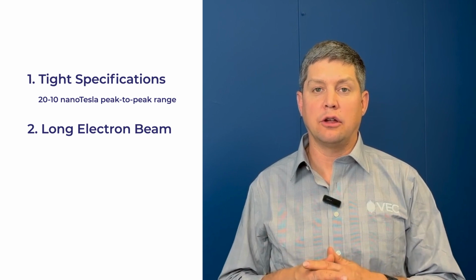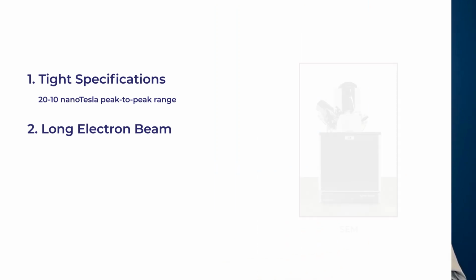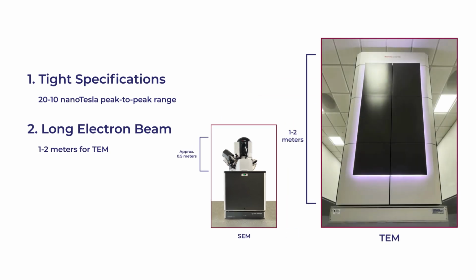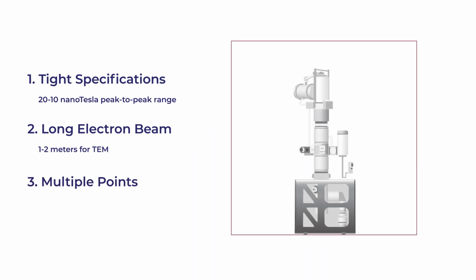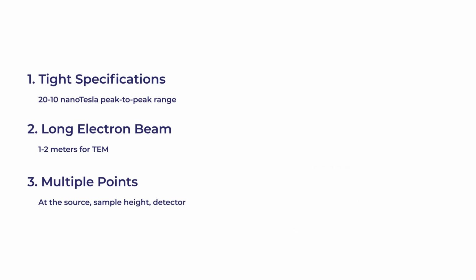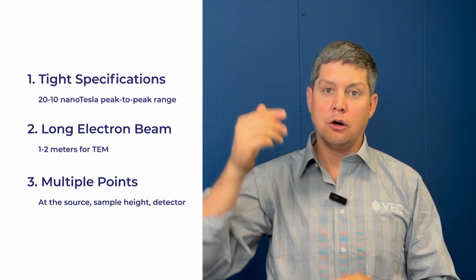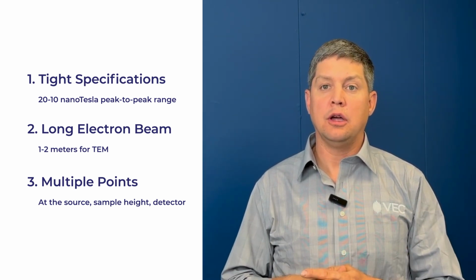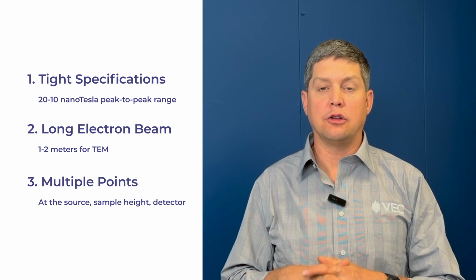So unlike a SEM, or scanning electron microscope, which has an electron beam column of only a couple feet, a transmission electron microscope can have a column length of a couple meters. And then the third reason is there's multiple points along the electron beam column that require this very tight specification. So oftentimes there's 3 points of measurement: the source, the sample height, and then the detector at the bottom. And because the specification is so tight and the points that require the very tight specification are far apart, a couple meters apart, achieving that tight specification is often very challenging.